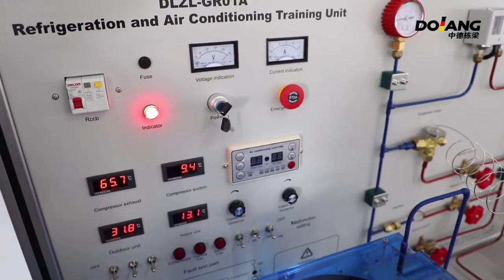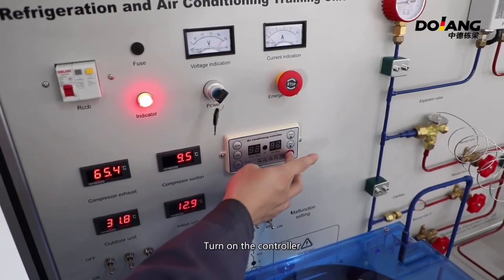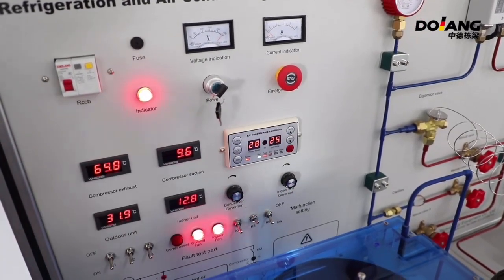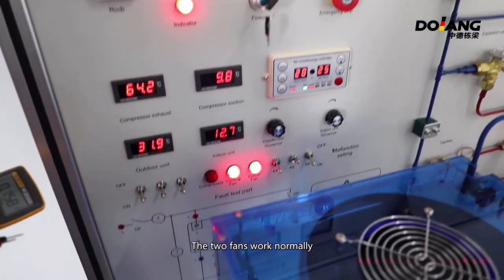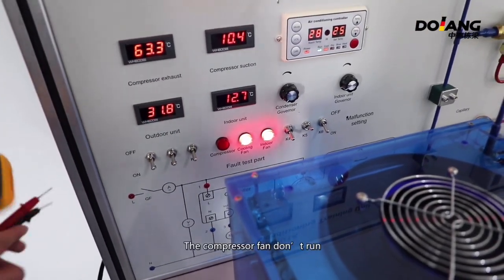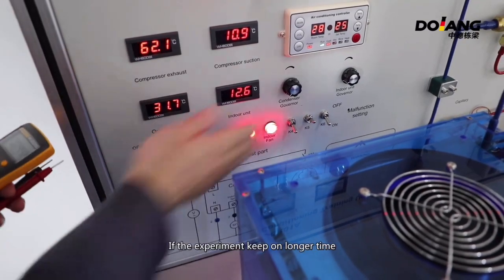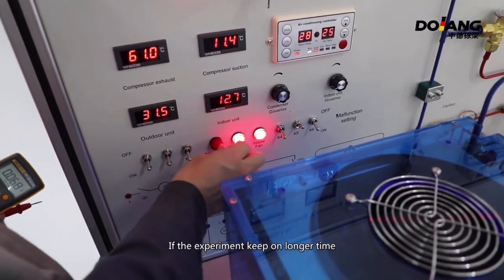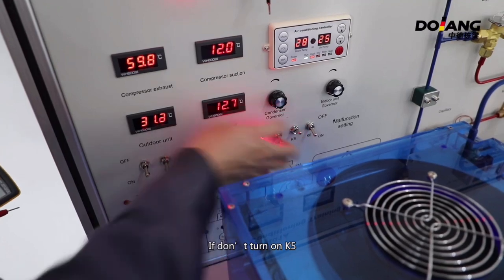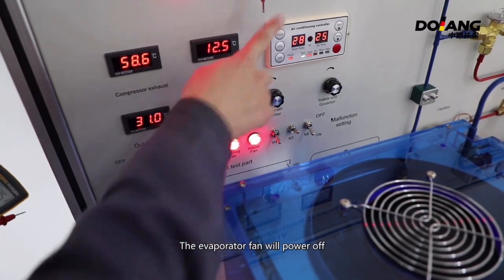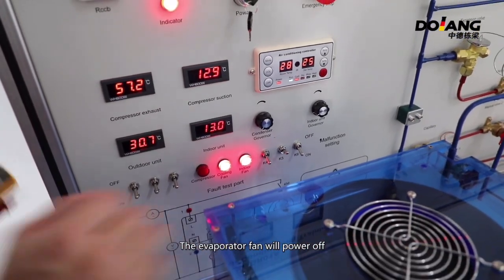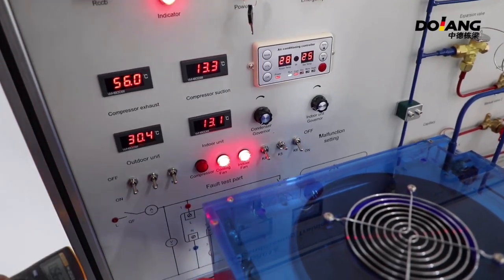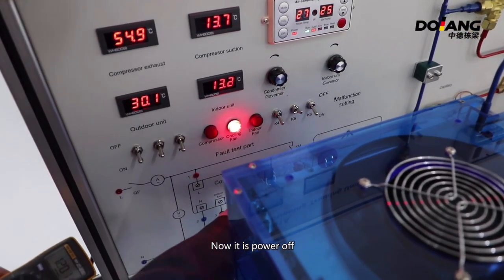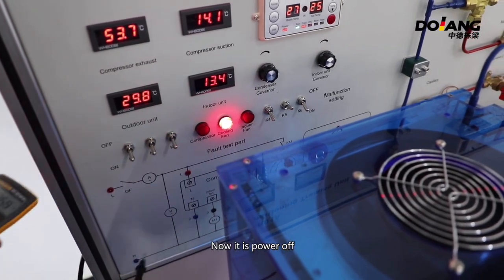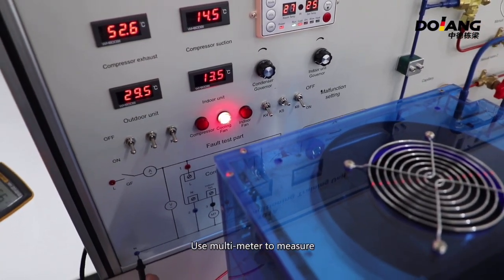Now do the fifth fault experiment. Turn K5 to off. Turn on the circuit breaker. Turn on the key switch. Turn on the controller. The two fans work normally. The compressor fan doesn't run. If the experiment keeps on for a longer time, if you don't turn on K5, the evaporator fan will power off. Now it's power off. Use multimeter to measure it. Means it's a compressor fault.